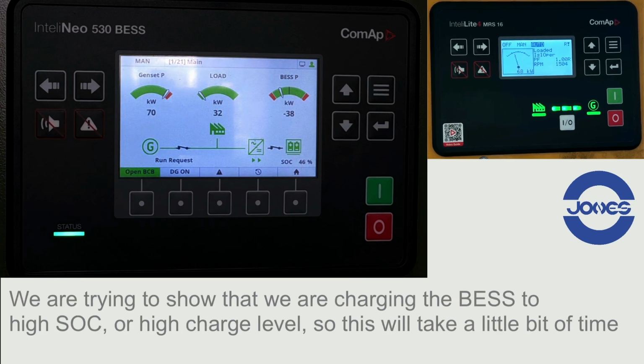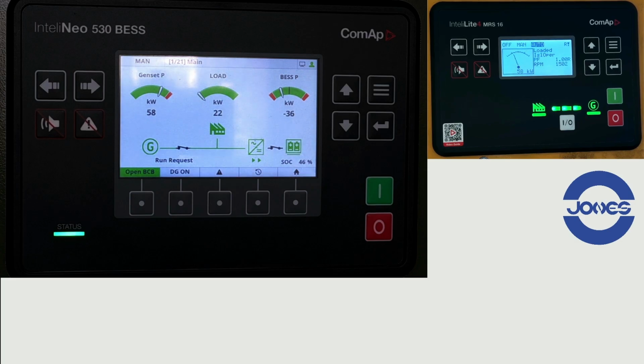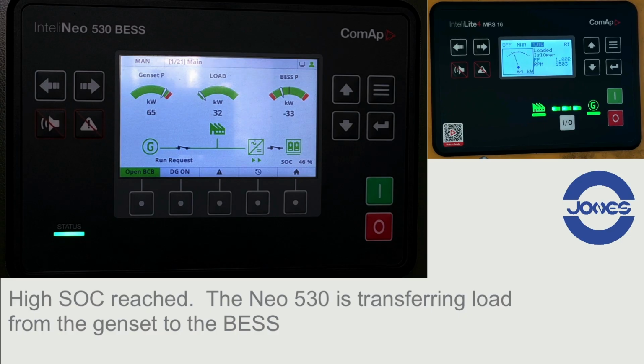We are trying to show that we are charging the BESS to high SOC, or high charge level, so this will take a little bit of time. As we do not want the demonstration to be too long, we have simulated a high SOC reached. So high SOC is reached, and the Neo 530 is transferring the load from the genset to the BESS.